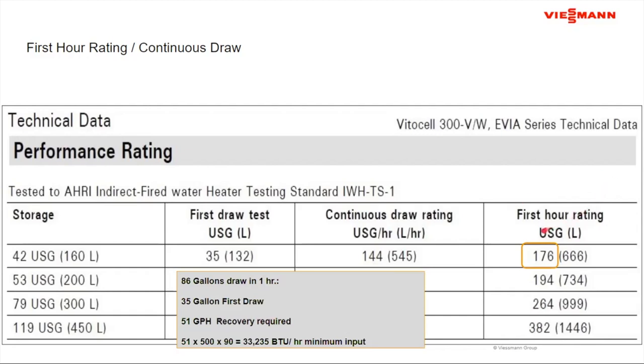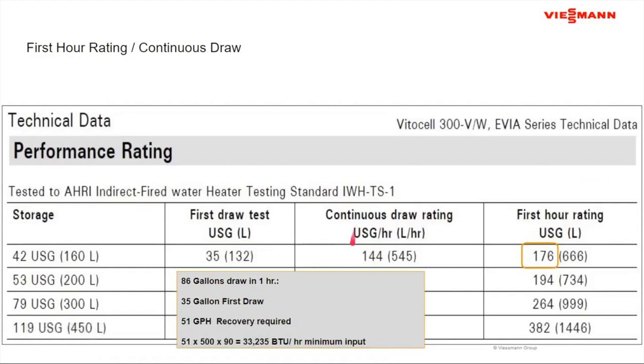And in fact, I don't need 176 gallons per hour, so I'm not really even interested in how they did it. What I do know is during the first hour, I can get 35 gallons of hot water out of that tank. So if I have 86 gallons that I need and I get 35 out of the tank, that's telling me I don't need a continuous draw of 144 gallons per hour. I only need a first hour draw of 51 gallons.